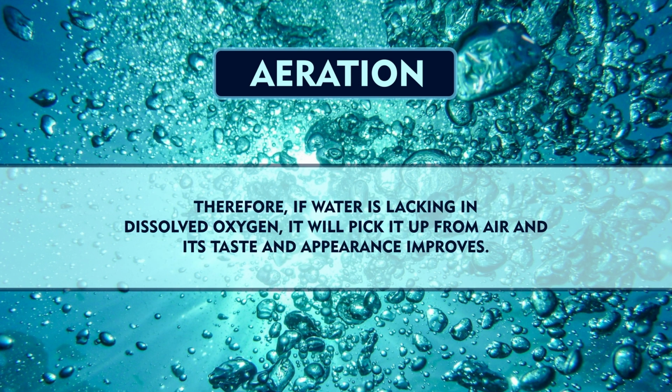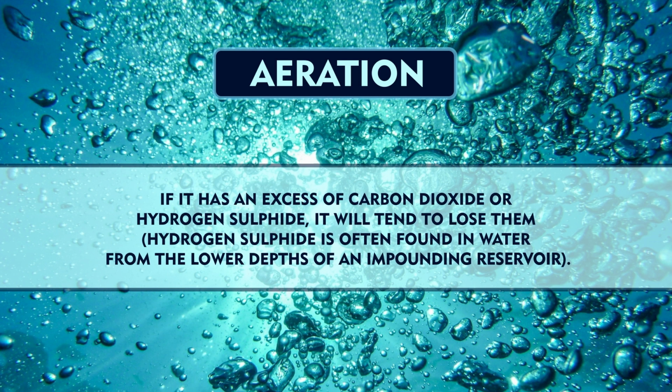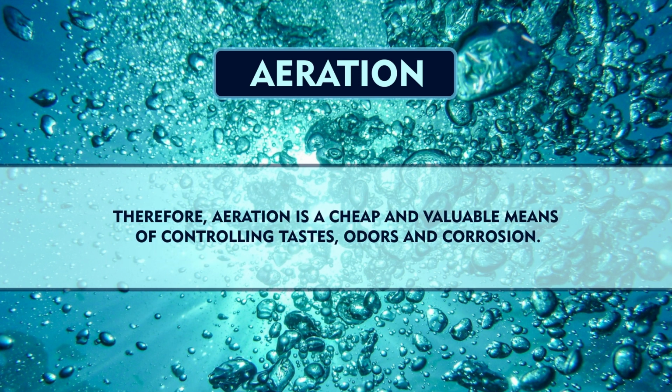Therefore, if water is lacking in dissolved oxygen, it will pick it up from the air and its taste and appearance improves. If it has an excess of carbon dioxide or hydrogen sulfide, it will tend to lose them. Therefore, aeration is a cheap and valuable means of controlling taste, odor, and corrosion.